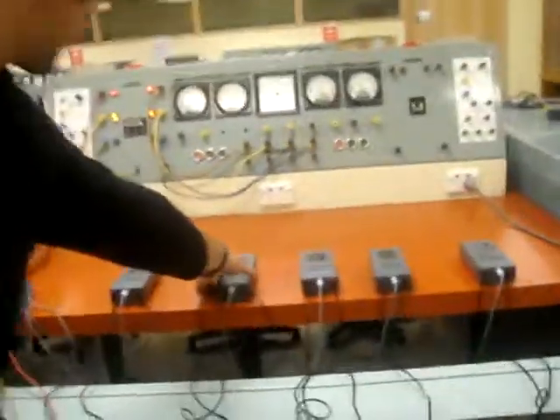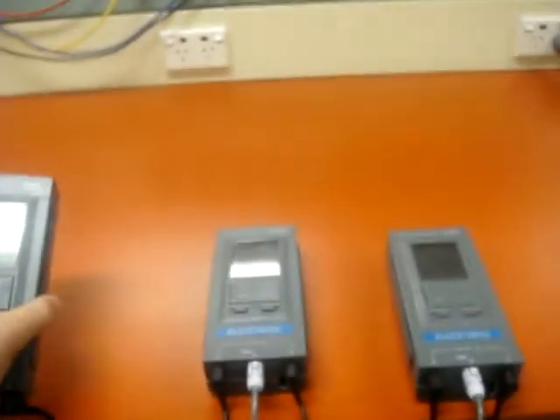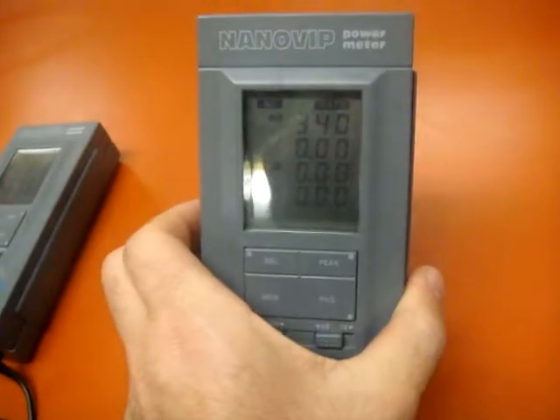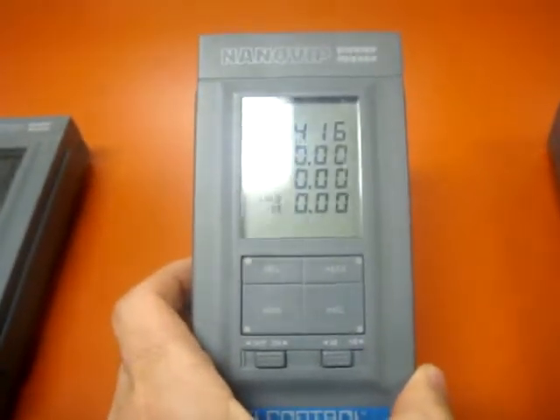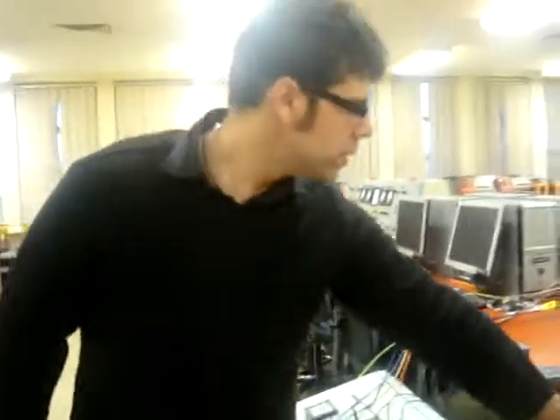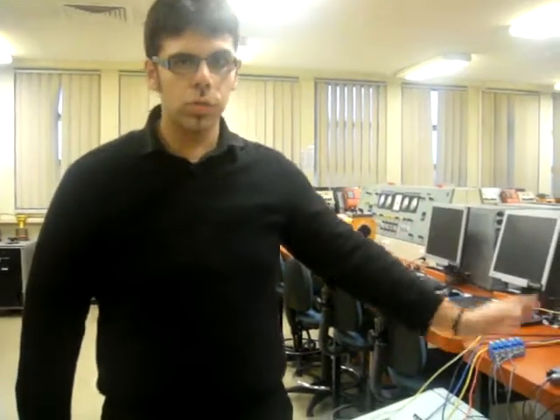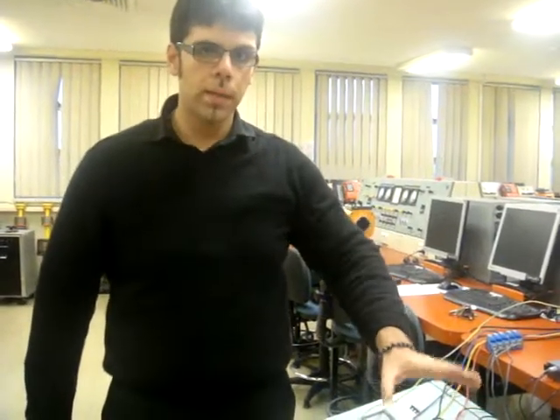If we have a look at Segment 1, it is also 415. Segment 2 is also 416. Segment 3 is 417. And eventually, we have 417 volts at our receiving end. Now, as you can see, there was clearly a voltage rise over the 300 kilometre transmission line. This is known as the Ferranti effect.